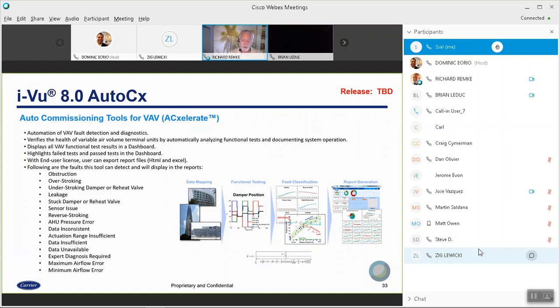What's great from an installer aspect is this is enabled for the first 6 months, and it enables itself when you first start using it. So it's great for doing commissioning and checkout. You'll be able to get a report quickly and say, oh, I've got issues with VAVs 1 through 10, however many VAVs you have on a job site, and you'll be able to go fix those through the report. If you are interested in doing service for your customer, you can sell them the license to do this, and I think it's on an annual basis that this will be licensed, so that they can continue to get these reports.